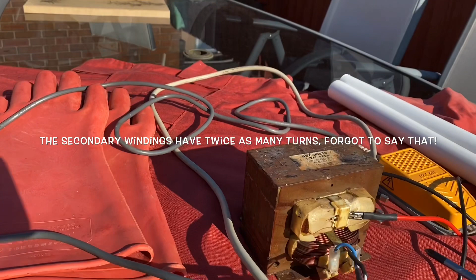The transformer works simply: 240 volts from the mains goes in via live and neutral to the primary windings, which step up the voltage by about 10 times. So 230 volts from the UK socket becomes roughly 2000 to 2300 volts output. It also steps down the current - from about 13 amps going in to about 1 amp coming out, at the chassis connection I've bolted on.